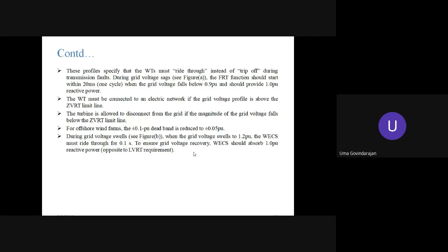The wind turbine must be connected to the electrical network if the grid voltage profile is above the zero voltage ride-through limit line. The turbine is allowed to disconnect from the grid if the magnitude of the grid voltage falls below the zero voltage ride-through limit line. For offshore wind farms, the plus or minus 0.1 per unit dead band is reduced to 0.05 per unit.